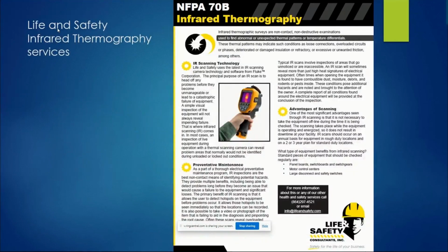So what do we do? Well, in life and safety, the biggest key element to this particular NFPA standard is to do the infrared scanning. It's a great tool, probably the highest demand tool we get for finding problems within your electrical equipment. When you ask us to come in, we give you a detailed report with pictures of exactly what we found, how to correct it, and recommendations, giving you everything you need to take to a contractor or do yourself in-house.